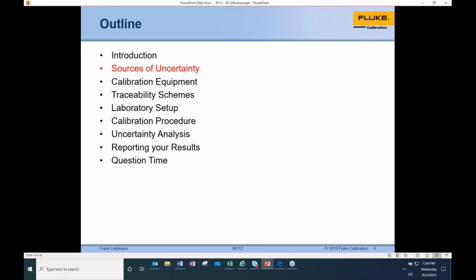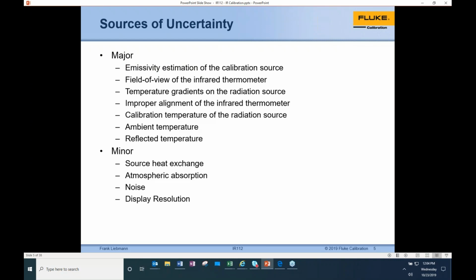All right, so we're going to first look at our sources of uncertainty and go through these different pieces here. Your major source of uncertainty, first and foremost, is going to be your calibration source. I don't know what you're using out there. Some people use the terminology of black body, gray body, IR cavity. All of these are going to have a different uncertainty associated with them based on if they're homemade, if they're manufactured, what the OEM specs are. So that's something really to consider. And on about the first three of these, then we jump down to the field of view of the actual infrared thermometer you would be testing, and then temperature gradients on the radiation source. Most of this information should be able to be sourced from the OEM or your user's guide on the pieces of equipment.